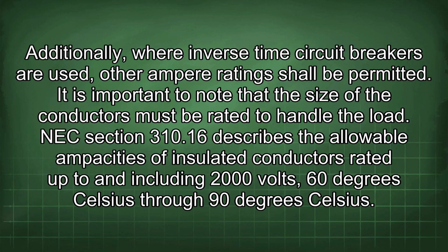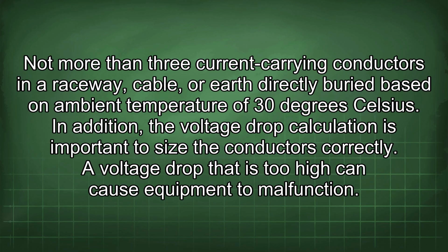It is important to note that the size of the conductors must be rated to handle the load. NEC Section 310.16 describes the allowable ampacities of insulated conductors rated up to and including 2000 volts, 60 degrees Celsius through 90 degrees Celsius. Not more than 3 current carrying conductors in a raceway, cable, or earth directly buried, based on ambient temperature of 30 degrees Celsius.